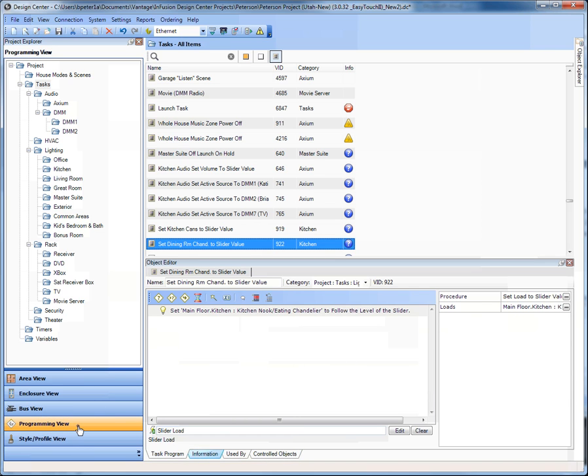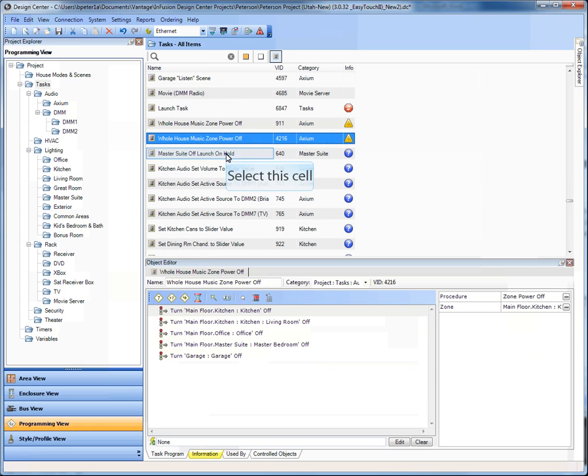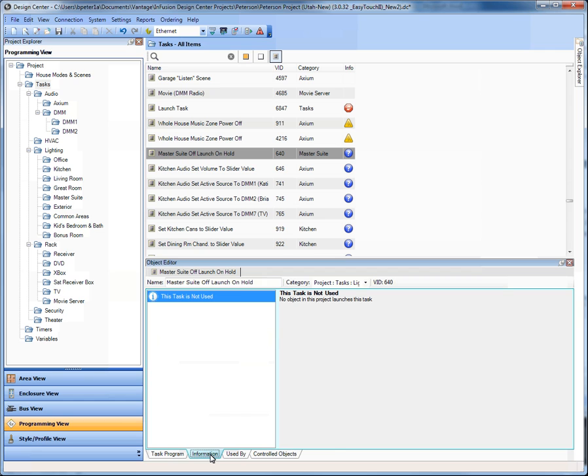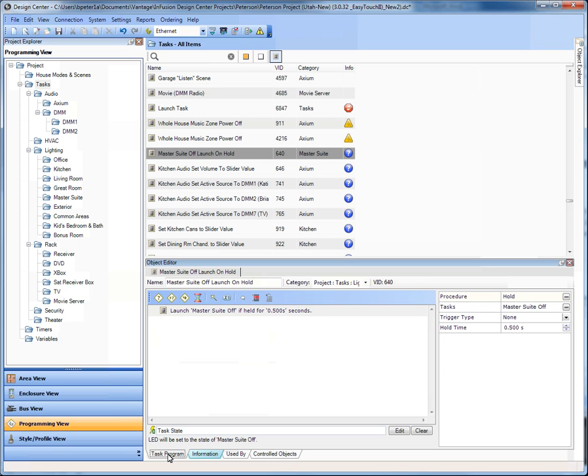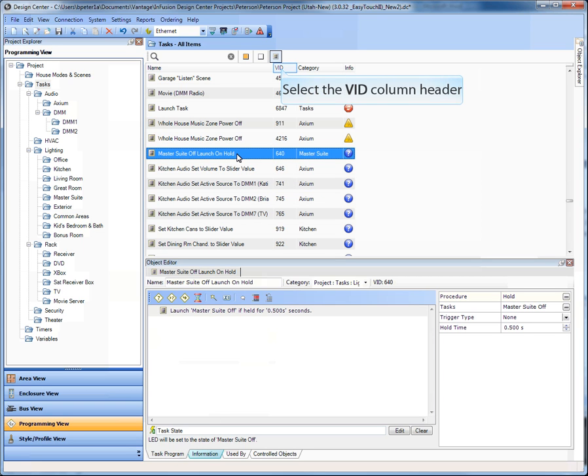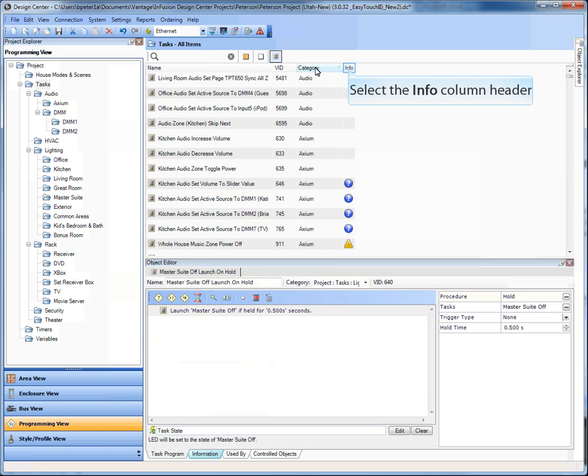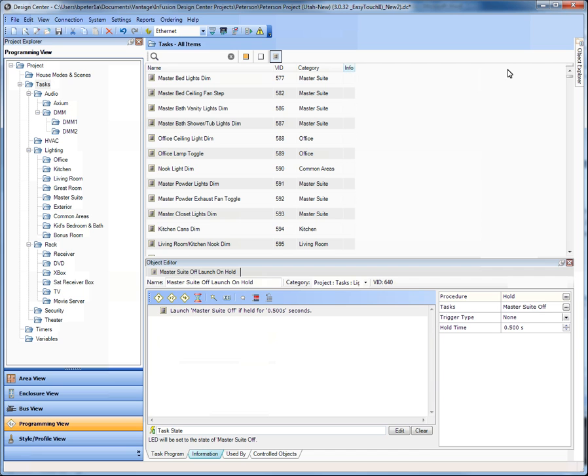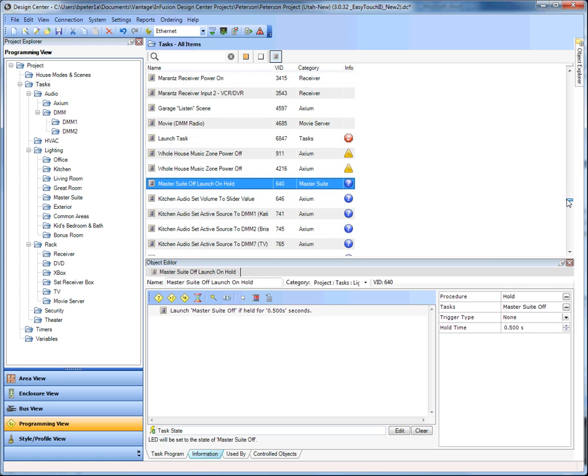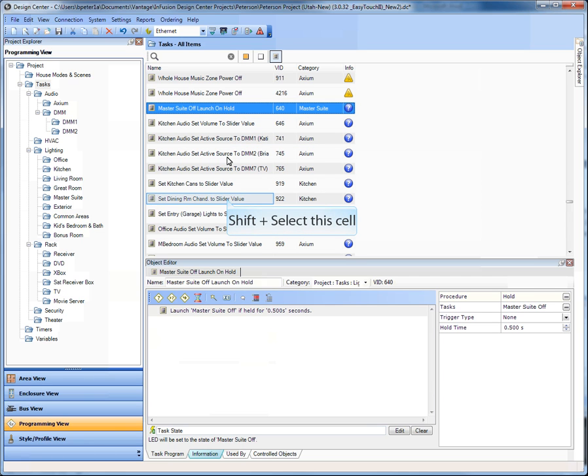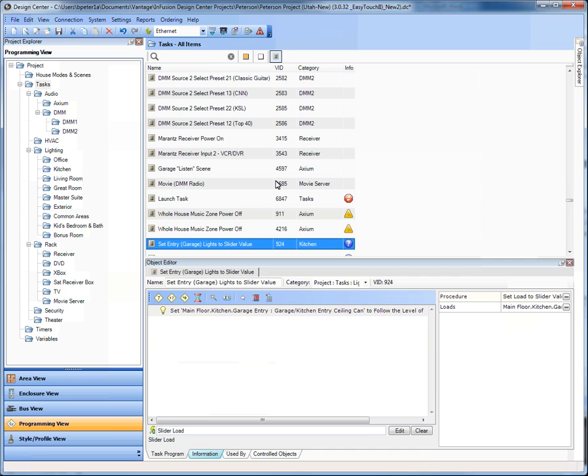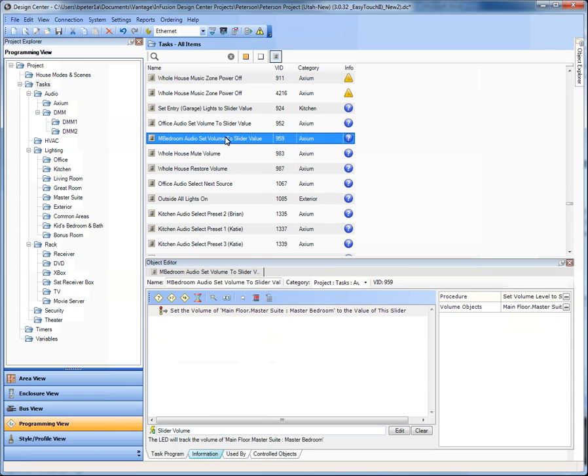What we're showing you now is the ability to look inside Programming View at what we've provided as the Info column. We've added a new column so you can see and sort by error message. Lots of times we have a little tab — blue, yellow, or red — down about the task, but it was hard to see all those together at one time. Typically it's due to unused tasks, looping tasks, or blocking procedures. So now you have the ability to sort by name, by VID, by category, or by the type of error message — by Info.